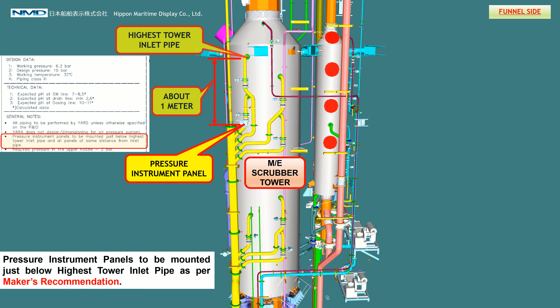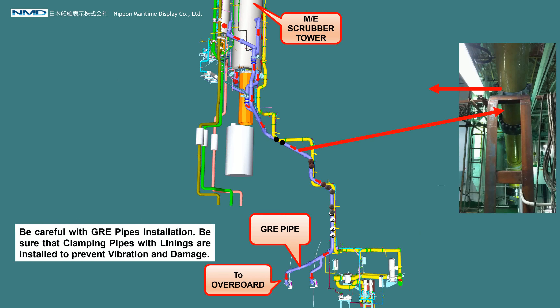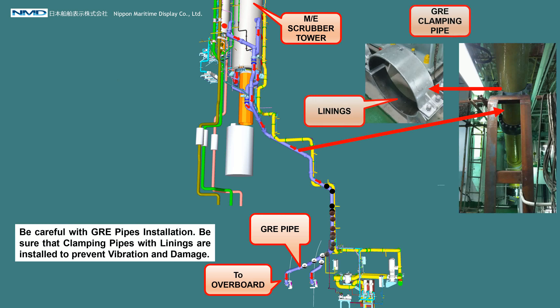Pressure instrument panels are to be mounted just below the highest tower inlet pipe as per the maker's recommendation. After cleaning exhaust gas with sea water, it will drain to overboard. Be careful with GRE pipe installation, and ensure that clamping pipes with linings are installed to prevent vibration and damage.